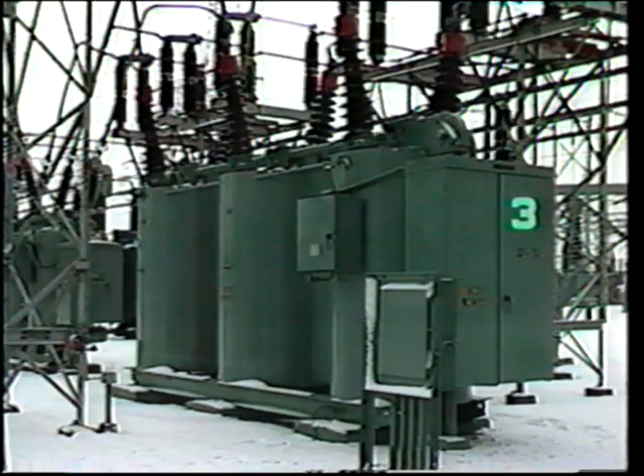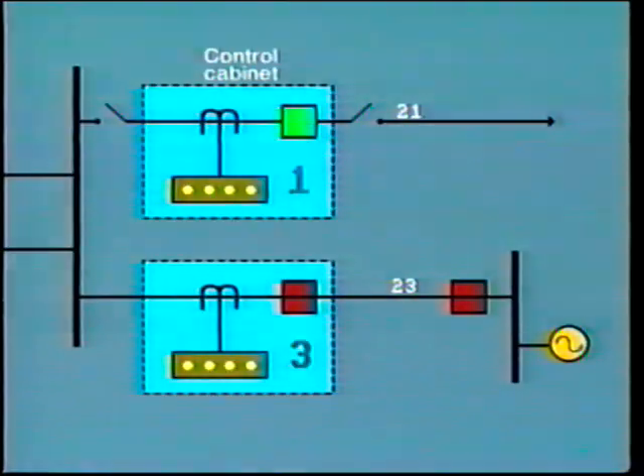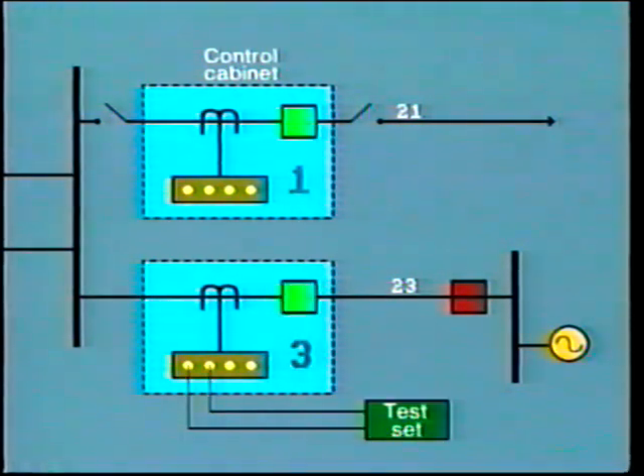The technicians left the relay house and opened the panel door at the nearest breaker. As it turned out, this was actually breaker number 3, and when they applied the test leads, the breaker tripped. A transfer trip was sent to the remote end of the line. As a result of this inadvertent trip, the remote generator was no longer in service.